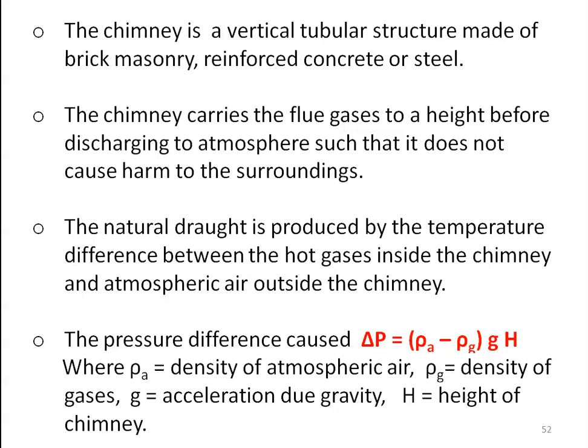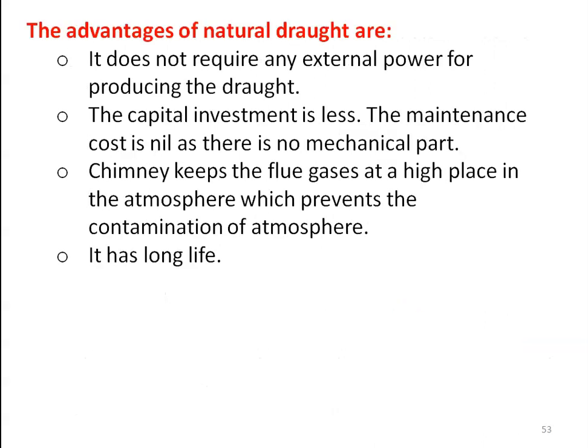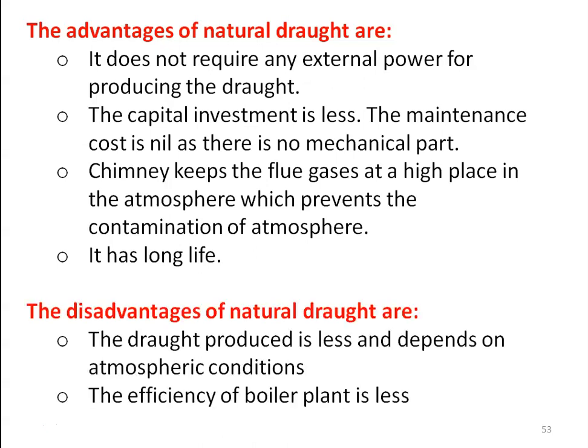Natural draught is very easy to maintain and a simple method. Advantages: it does not require any external power to produce draught, as it is naturally produced by temperature difference. The capital investment is less, maintenance cost is nil as there are no mechanical parts. The chimney keeps the flue gases at a high point in the atmosphere, preventing contamination, and has a long life. Disadvantages: the draught produced is less and depends on atmospheric conditions and chimney height, so the efficiency of the boiler plant is less. In modern boilers, only the artificial draught system is used.